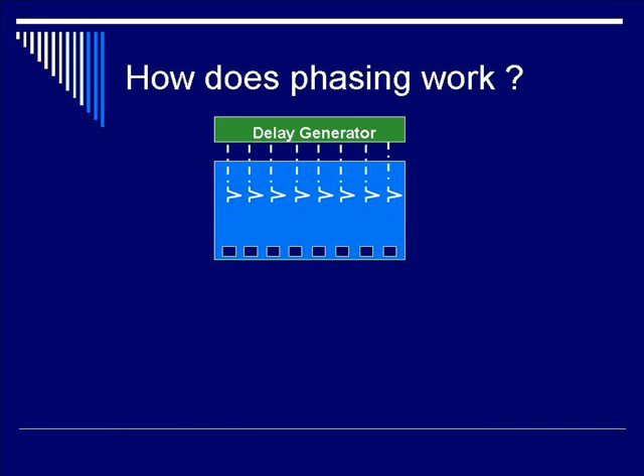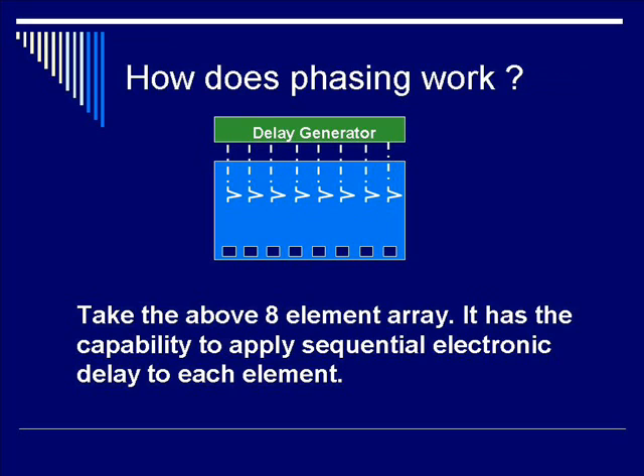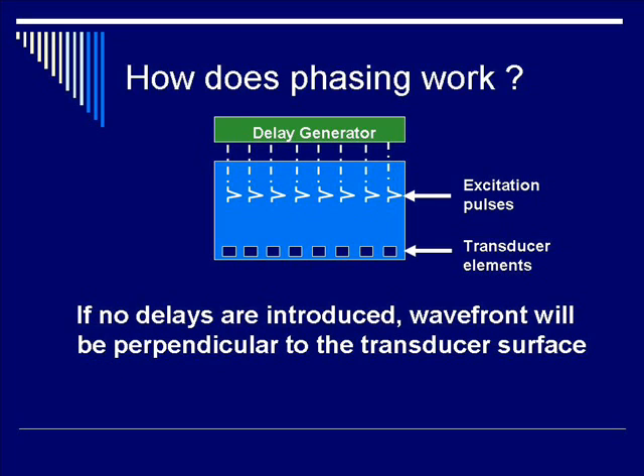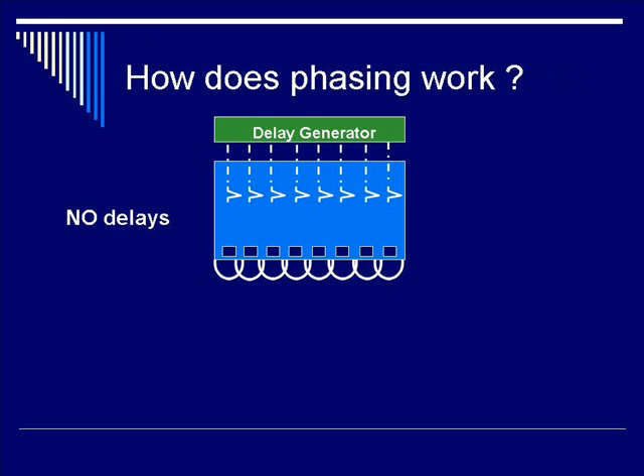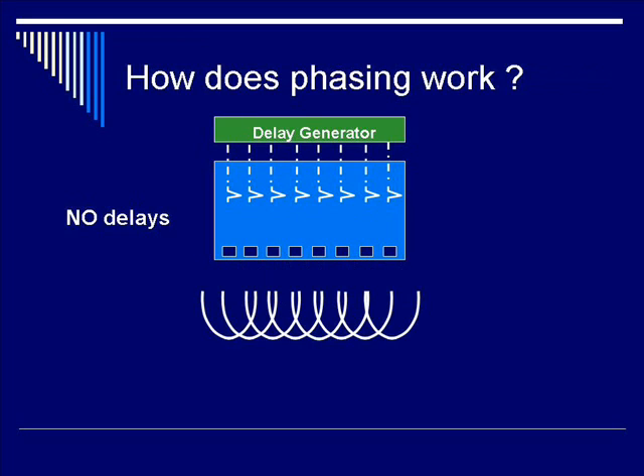Now how does phasing work? It involves an electronic delay generator attached to the back of the transducers. Here you have an eight-element array with the capability to apply sequential delays to each element. The transducer elements and excitation pulses are labeled. If no delays are introduced, the wavefront will be perpendicular to the transducer surface. With no delays, each element produces an ultrasound pulse with a characteristic wavefront that are in sync with one another. Therefore, the direction of the wavefront is straight ahead.